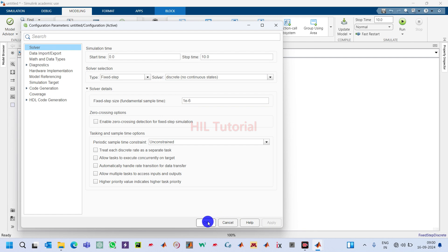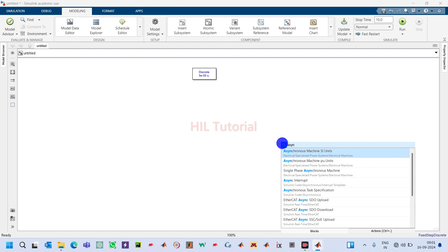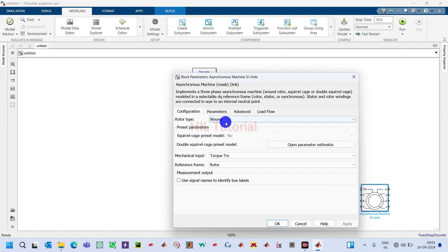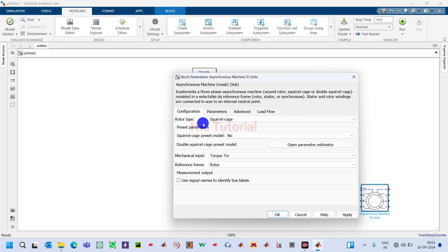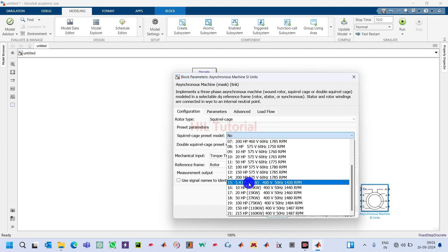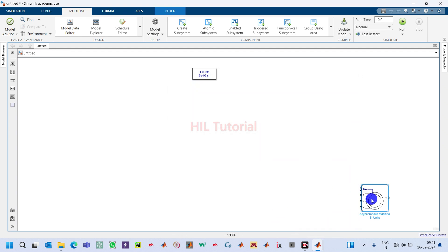Simply click Apply and OK. Now we will take one Asynchronous Machine block — Asynchronous Machine SI Units. Double click on it and set the rotor type to Squirrel Cage, so this becomes a squirrel cage induction machine. For the preset model, select the 5.4 HP, 400 V, 50 Hz, 1430 RPM option. Apply and click OK.